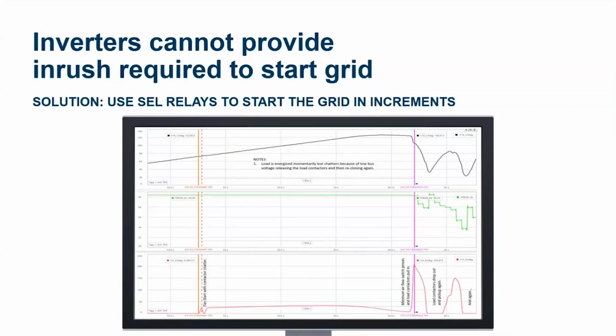Inverters are not forgiving. Their design margins are an order of magnitude smaller than the conventional generator. Here's an example of an inverter-backed battery trying to start a small load bank with a fan and a contactor and a transformer that in total equated to half of the inverter's nameplate. What you see is very common with inverter-based resources: it ramps the voltage to avoid the flux remnants in the steel of the transformer.